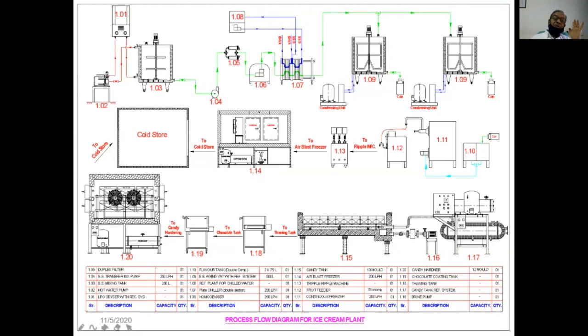So here this is the first unit where we require refrigeration for cooling the mix from 65, 70 degrees to 6 degrees or 4 degrees. This is the plate type heat exchanger where we feed the hot mix from one side and the cool mix comes out from the second side. It is cooled by well water, cooling tower water, and chill water. You can see here it is a two-stage cooling. First cooling is done by well water, so we can save energy, and then further cooling is done by the chill water.